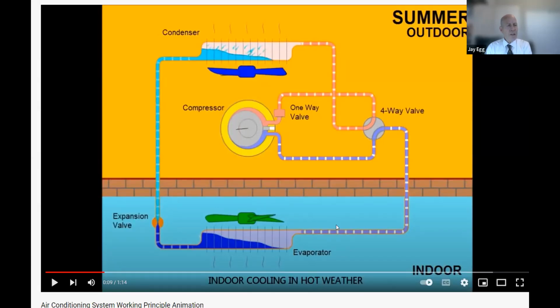And using this in the summertime when it's hot outside, the compressor creates hot gas. It's just a compressor like an air compressor, but it's using a closed refrigerant system, and it compresses hot gas, then it runs it into a condenser, which is what is considered the heating coil of the refrigeration system. And that condenser condenses refrigerant, and as it does it, it creates a heating effect. After it goes through the condenser, you have a high pressure liquid that goes through an expansion valve, which drastically drops the pressure and begins the evaporation process of the refrigerant.